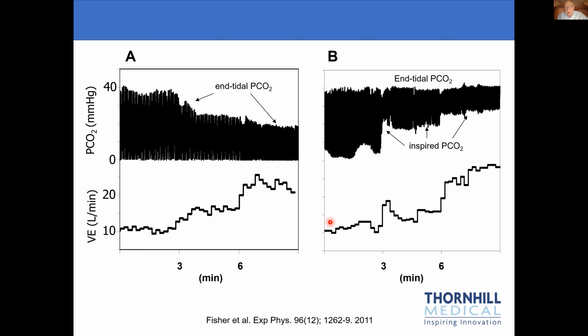So here I hyperventilate, and this is my end-tidal PCO2, and this is my inspiratory PCO2. And you can see from the pattern here that the harder I breathe, the higher the inspired concentration of CO2, such that my end-tidal and my arterial PCO2 stay constant, independent of how I breathe. And this is much more accurate than what you can do with a computer, because this is foolproof. There's no algorithm to make a mistake. It's completely mechanical.